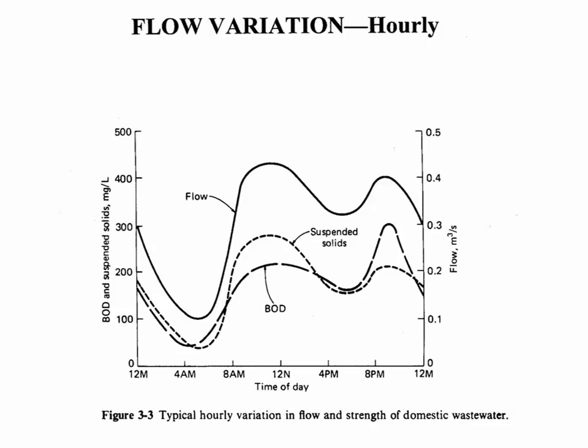But then during the day, it's more deliberate discharge. A greater fraction of what's in the sewer is going to be from people flushing their toilets, and food particles. The food scraps that get ground up in a garbage disposal and washed down into the sewer, that increases the BOD a lot. And the same thing is true of suspended solids. It's just in the middle of the night, less of the wastewater is intentionally flushed, and during the day more of it is. So that talks about the temporal variation, not only of the quantity, but in the strength of the waste.